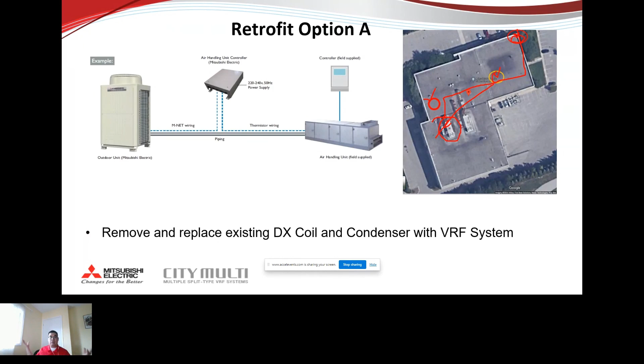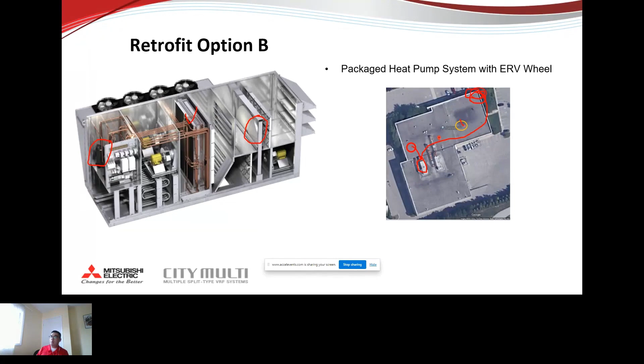The second option is to completely remove and replace this rooftop unit with a packaged heat pump system with an ERV wheel. So the compressor will be able to provide heating and cooling for the DX coil, and we're able to use the ERV to still have effective heating and cooling. It will be very, very efficient compared to the existing system because we are using an inverter-driven compressor as well as an ERV. However, the problem that still remains is that I have the same discharge air temperature coming off the coil, but it has to travel all the way to the other end of the building, versus this person over here and me over here. So that may not be the most comfortable solution.